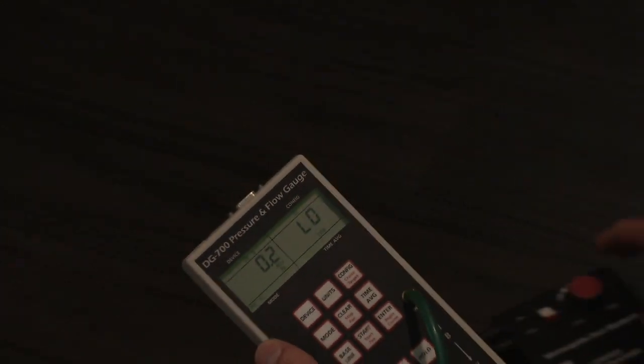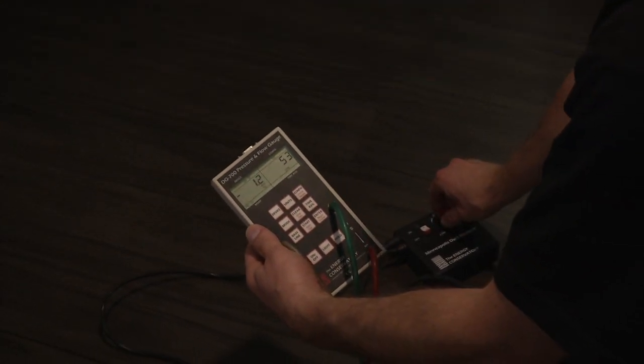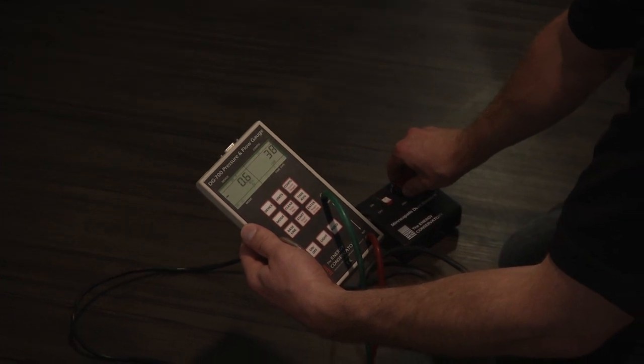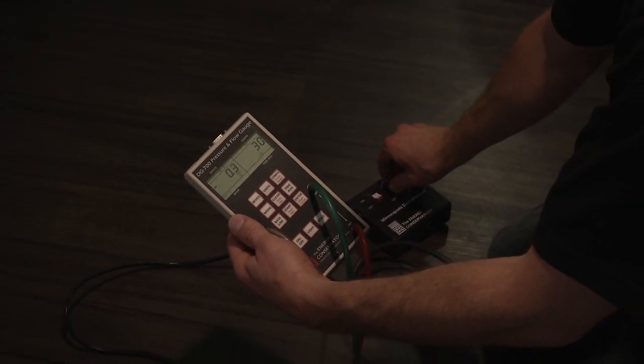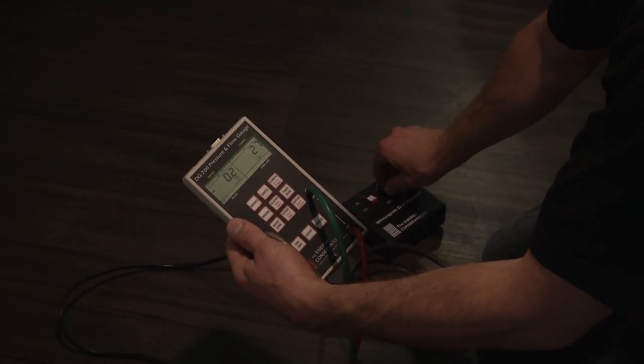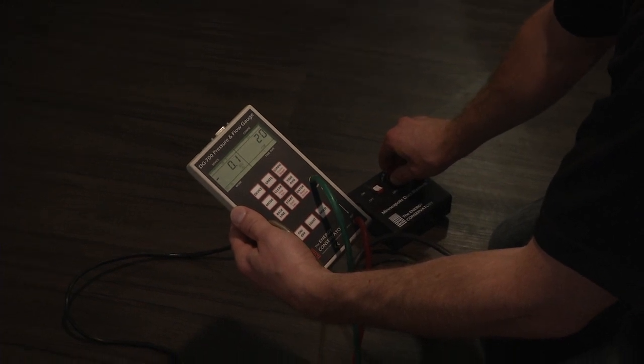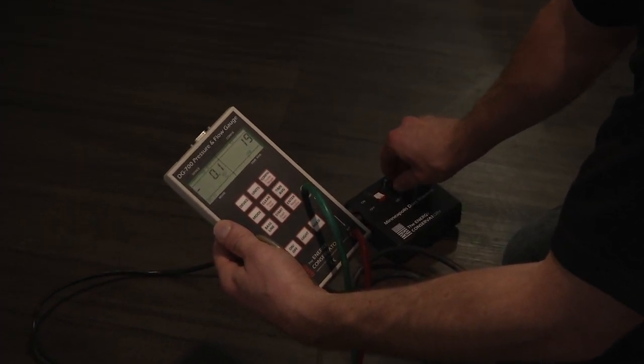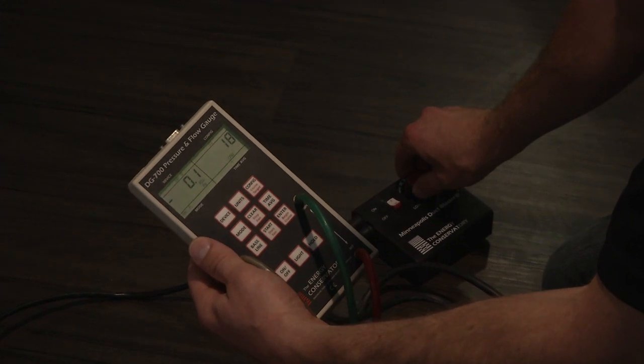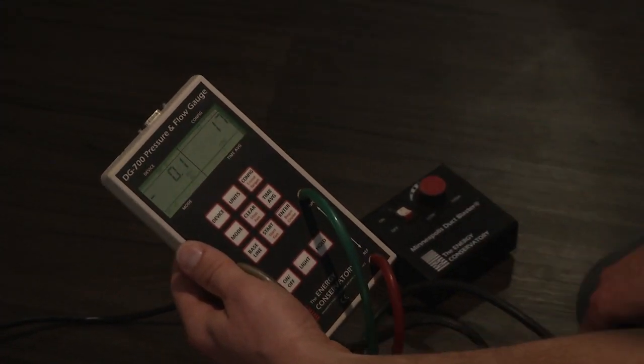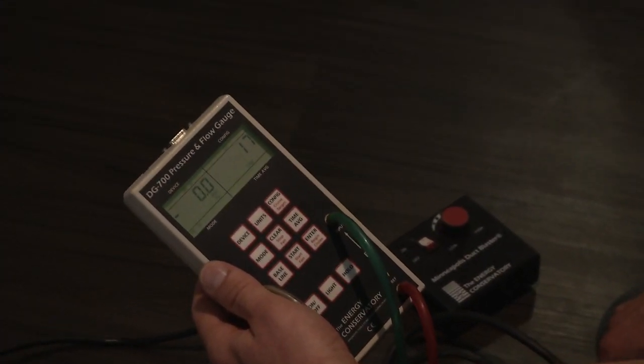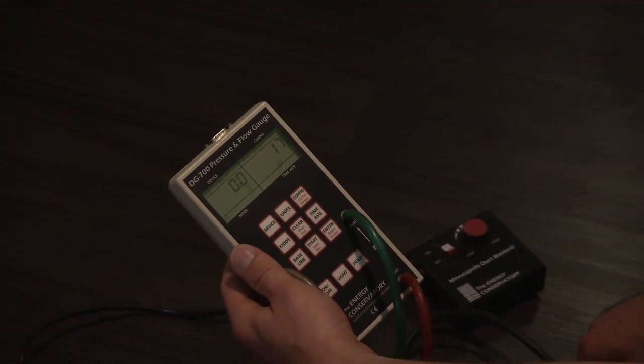So I'm going to use this right here to turn it on. And I need just to back it down until it gets to 0. And once it hits 0 on the left-hand side, it looks like we're going to be at about 16, 17 CFM of duct leakage to outside.